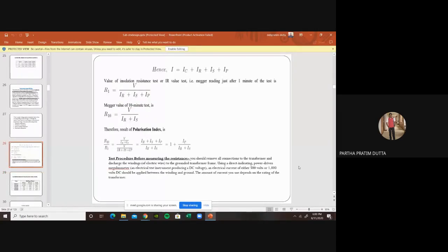If we denote them IC plus IR plus IS and IP, hence the total current should be I. So the value of the insulation resistance test, or IR value test, or megger reading just after 1 minute of the test, is R1 equals V by (IR plus IS plus IP), and the megger reading for the 10-minute test is V by (IR plus IS). Therefore, the polarization index would be R10 by R1, as I told you. If you cancel the V, then (IR plus IS plus IP) by (IR plus IS), if you divide these two, it comes to 1 plus IP by (IR plus IS). That means it should always be greater than 1. That is how we determine that polarization is perfect and insulation is perfect.